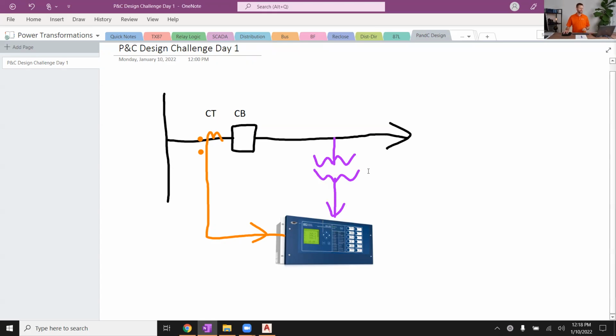But this is going to be our PTs, okay? This is not a power transformer. This is a potential transformer, sometimes also called a VT, a voltage transformer, where it's bringing in a measurement of the voltage. Again, this is a one-line equivalent. There would really be three PTs and three CTs in this set. So these are the inputs coming into the relay as far as AC inputs.